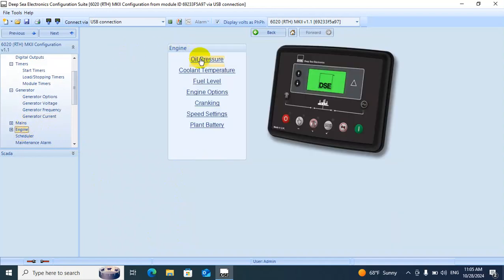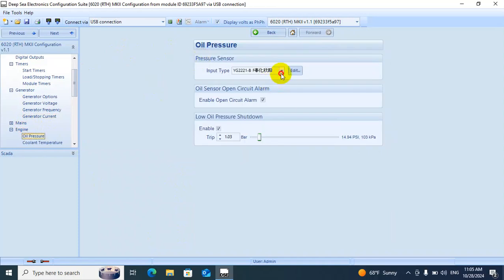Engine oil pressure. We are coming to oil pressure. Now we have to choose the type of sensor. If we are changing the sensor and we couldn't find the same sensor, and we want to fix another one like a VDO or other, we have to choose it from here. Now we will keep it as it is. Oil sensor open circuit is enabled. In case we remove that wire from the oil sensor, the generator will give an alarm. And low oil pressure: when the sensor reading is less than about 1.03, the generator will go to shutdown.